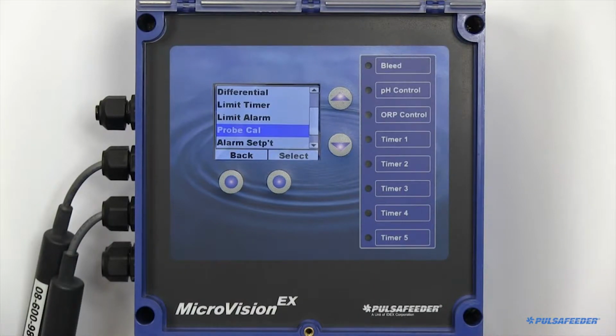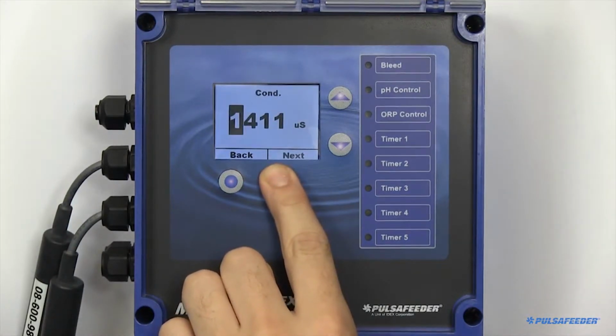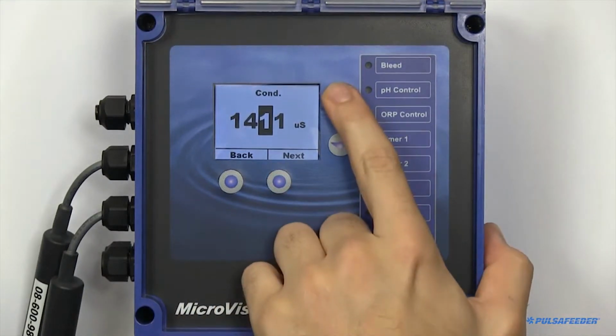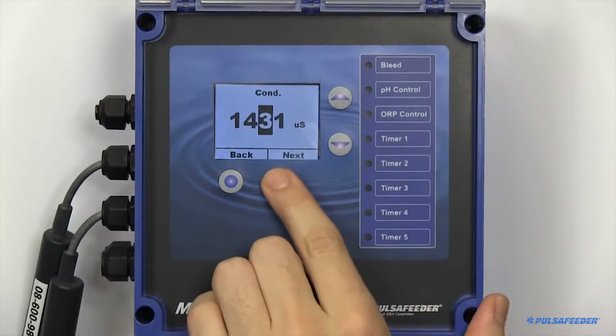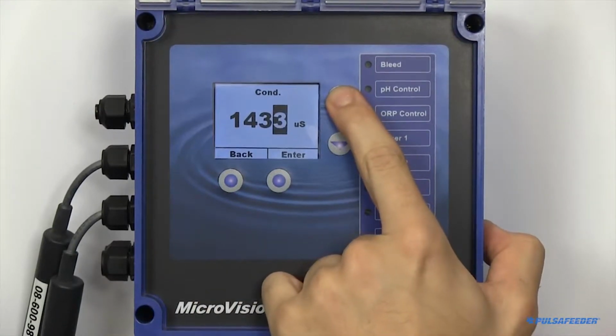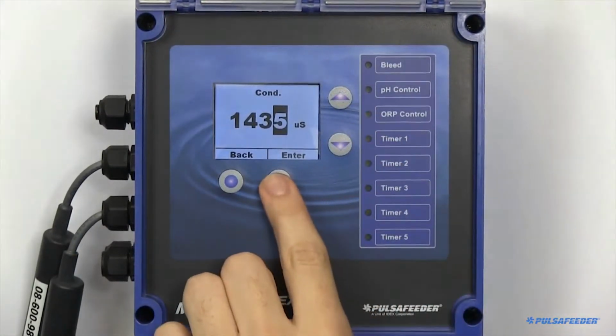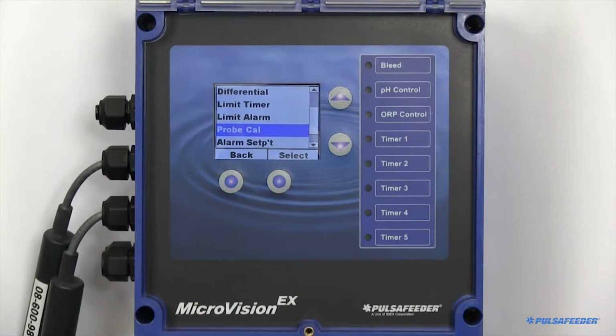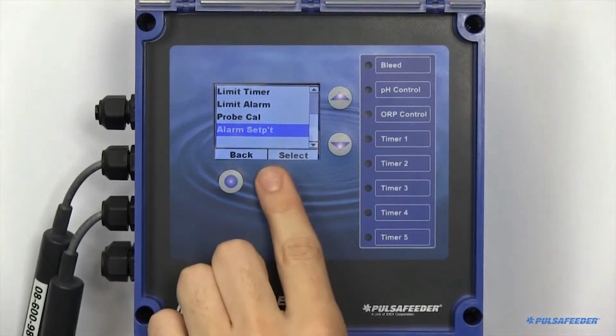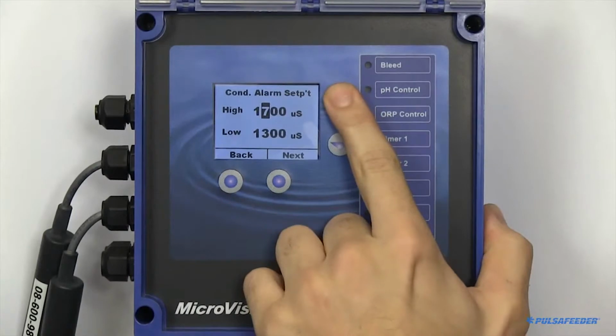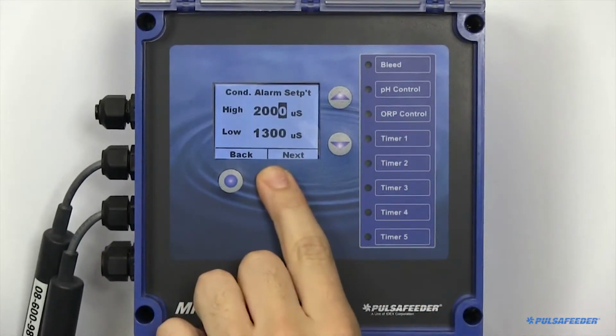Calibration of your probes is also essential. Some things to remember is that temperature fluctuations can affect some readings. Make sure the probes are in the desired solution for a minimum of 10 minutes. If using a handheld to calibrate, also make sure the handheld has temperature compensation. High and low alarms can also be configured. These are values which, if the reading goes beyond, will trigger an alarm.